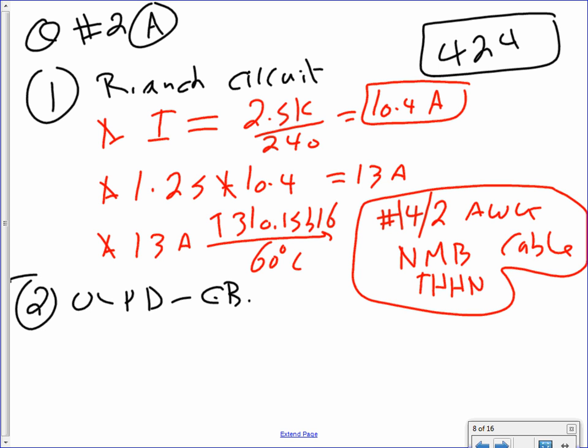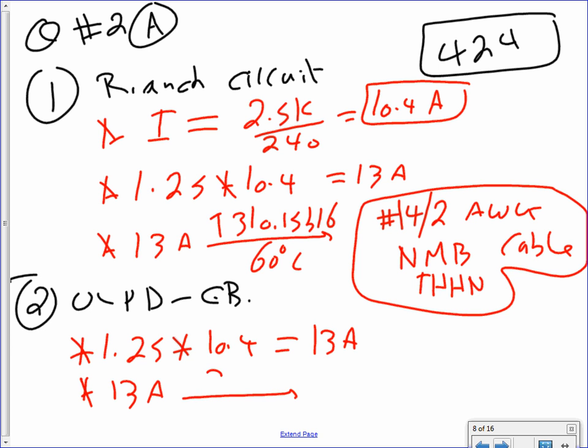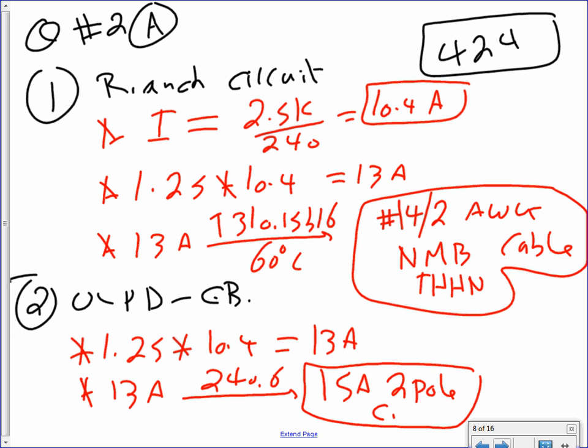Overcurrent protection device, the circuit breaker, is a piece of cake. Same calculation, 1.25. Multiply this baby by 10.4. It will get 13 amps. You take the 13 amps to 240.6. That will get you a 15 amp 2-pole circuit breaker.